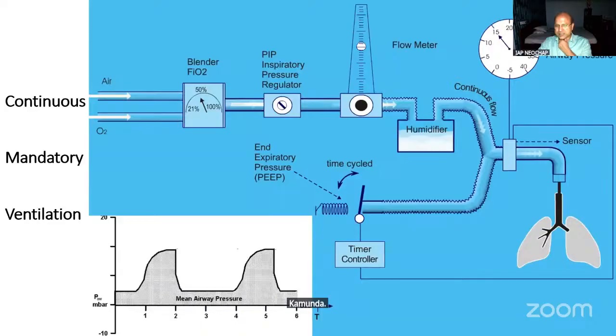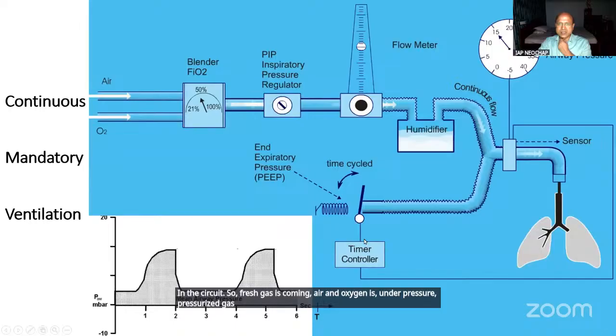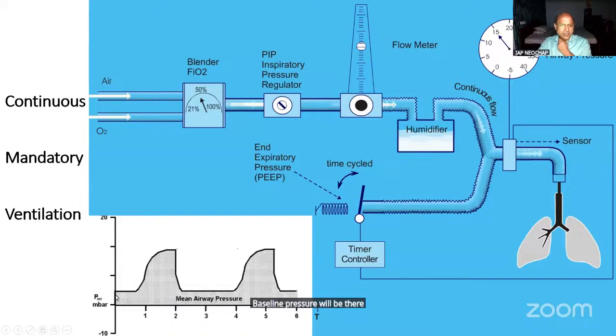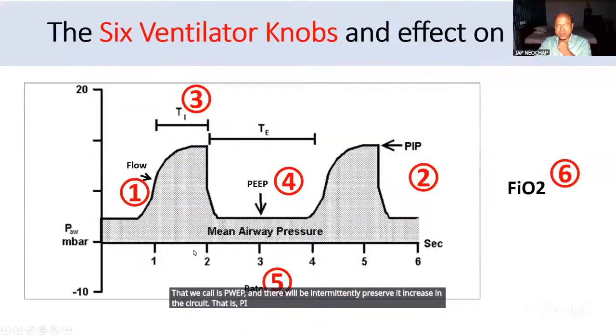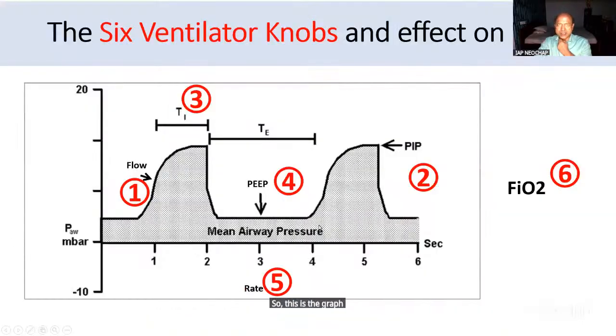Coming to how the ventilator works. The ventilator works by increasing the pressure in the circuit. So fresh gas is coming, air and oxygen under pressure, a pressurized gas. And here is a valve, and this keeps on opening and closing, and this will create a baseline pressure, that we call PEEP, and intermittently the pressure will increase in the circuit, that is PIP. So this is the graph.